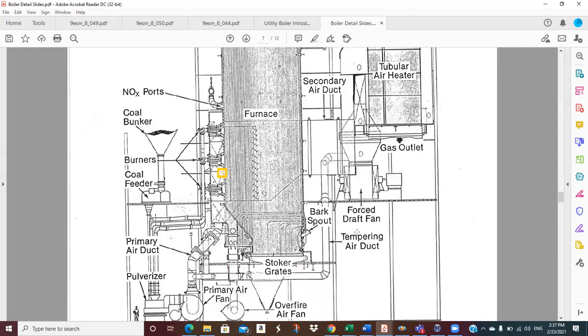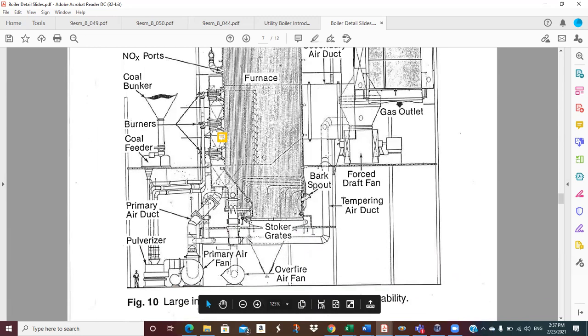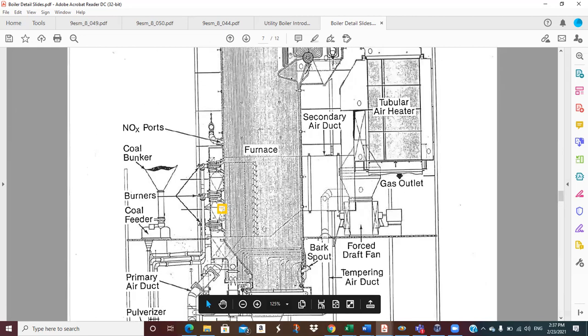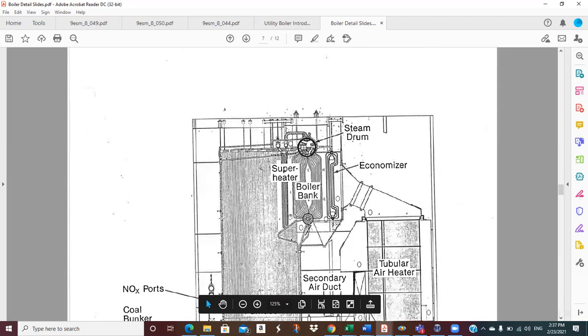What else we got here? Forced draft fan, tempering air duct. That's to feed in case, let's see, in case this was to be too cold over here, we can circulate some of this hot gas back over to the primary fan and overfire air. So it's got a couple of fans on it, but that's pretty much what's going on.